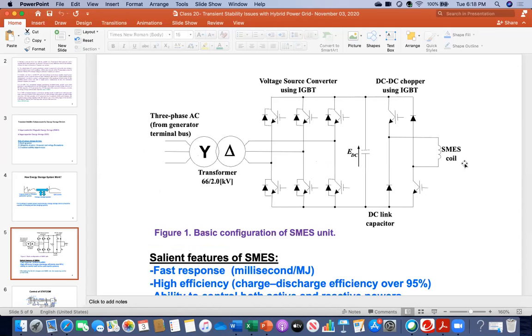The whole thing is called the SMES unit, superconducting magnetic energy storage unit. The components include first a Y-delta connected step-down transformer. For example, if the grid or generator terminal voltage is 66 kV, it is stepped down to 2 kV, because the power electronics devices have certain voltage withstanding capability, so you must convert to a voltage tolerable for the power electronic device.